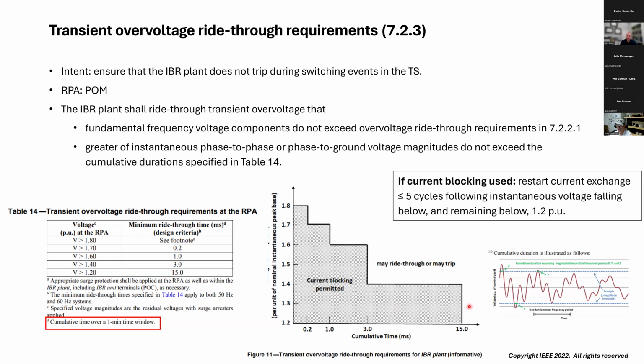Another important note is current blocking is permitted once the POM instantaneous voltage goes over 1.2 per unit. However, you need to start current injection within 5 cycles of that voltage going back down below 1.2 and staying below 1.2.